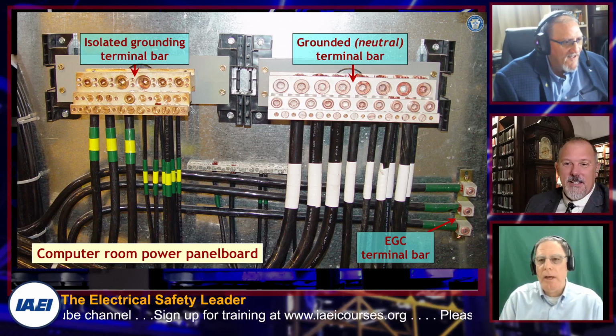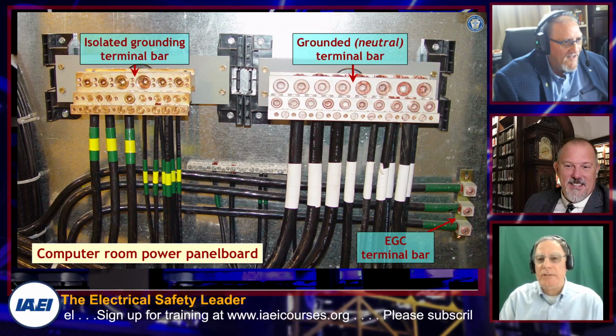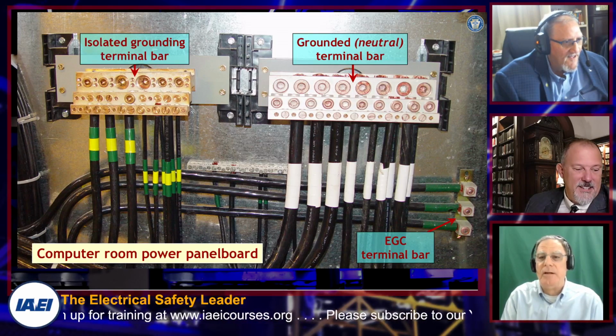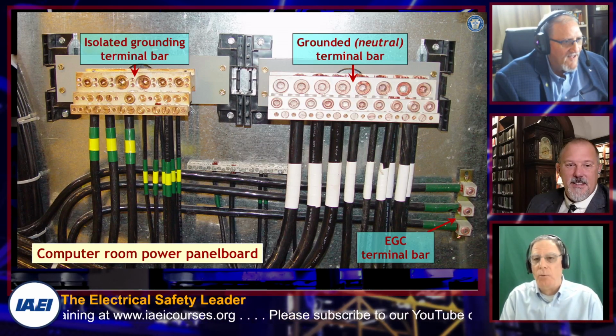There's a funny story, I know of an installation in Los Angeles that's exactly how the main bond jumper is identified, because one inspector required white since it's hooked to the neutral, and another inspector came along to try and get service energized and said no, that's hooked to ground, make it green. So it's actually a barber pole of white and green going down the whole main bond jumper for a 4,000 amp service.